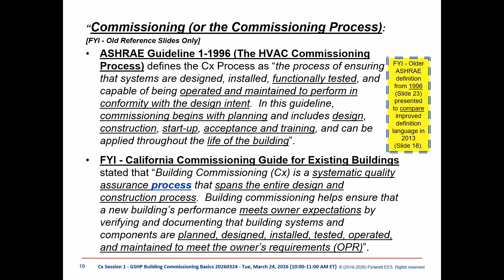Why commissioning here? To ensure correct geothermal system operation, controls, and integration with existing HVAC systems, energy management control systems, and heat distribution systems. Again, integration is a key point. You are not just installing a well field or a heat pump. You want to make sure that well field and heat pump work with the existing mechanical systems, which could be hydronic, could be air, could be a mixture of air and hydronic, radiant slabs—just make sure it's all integrated together.